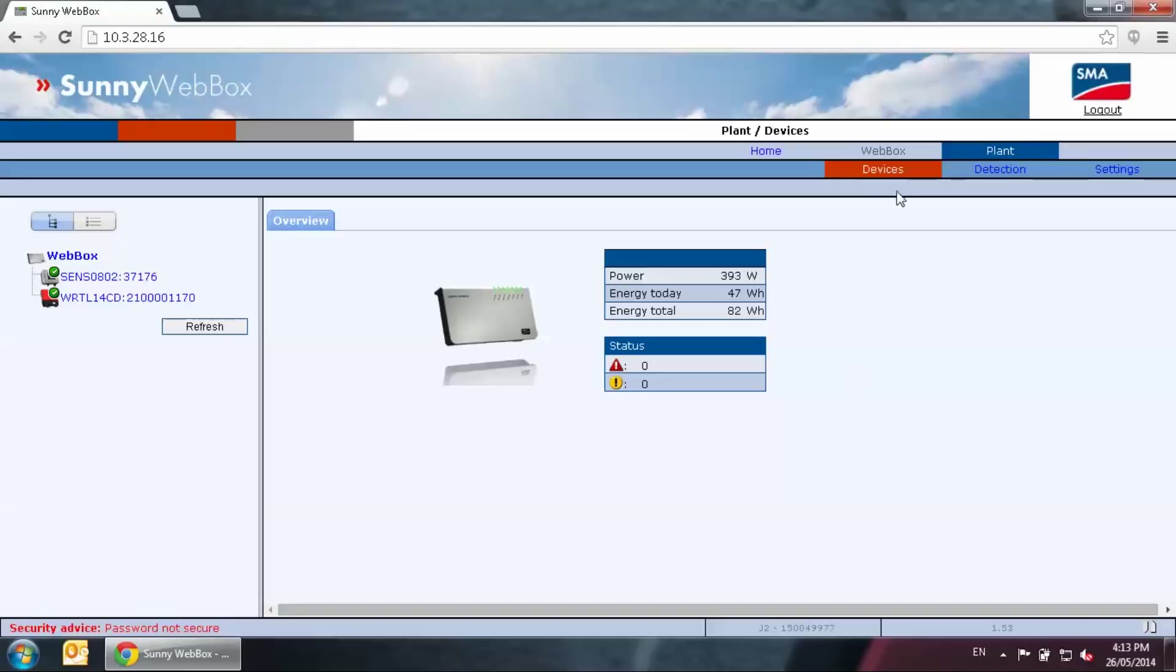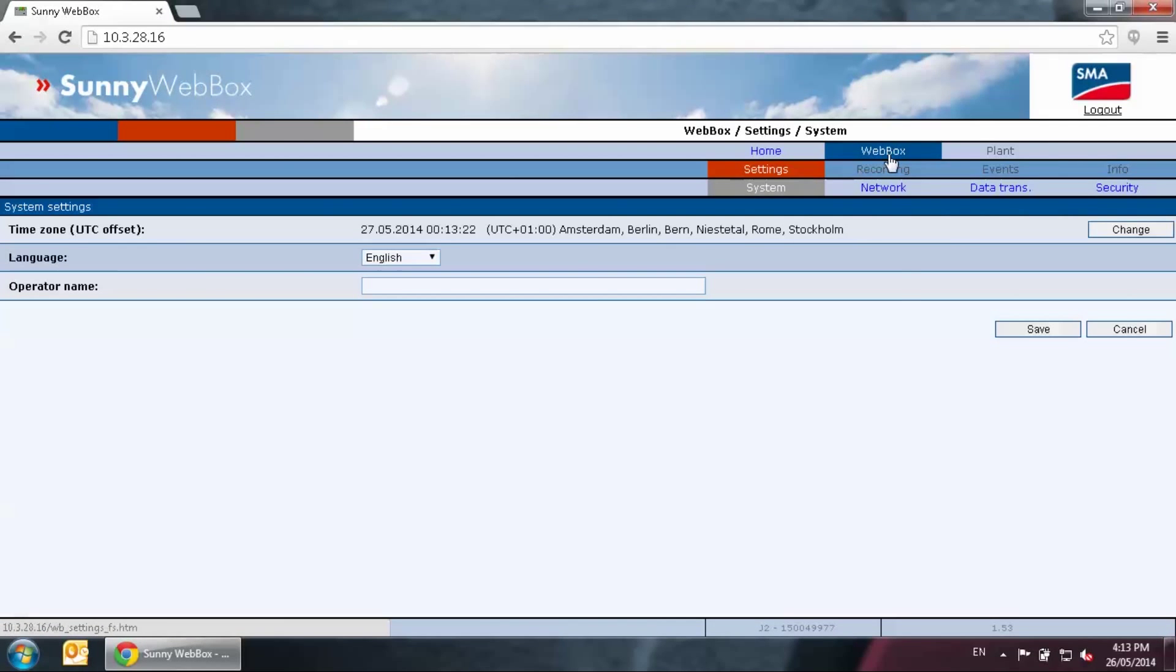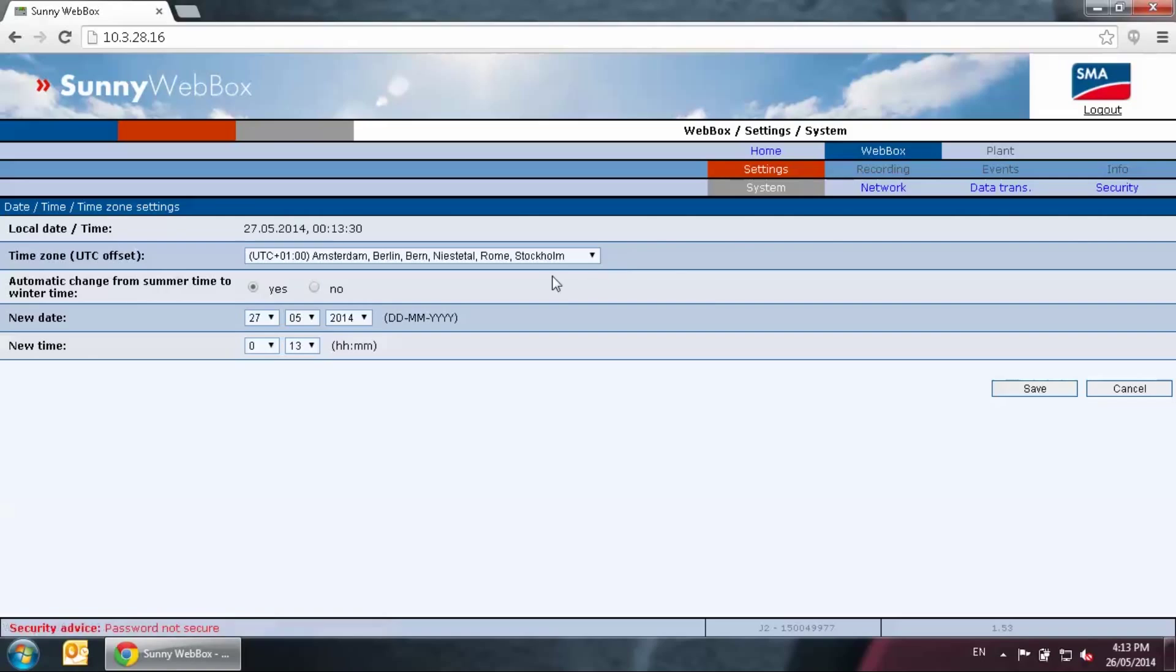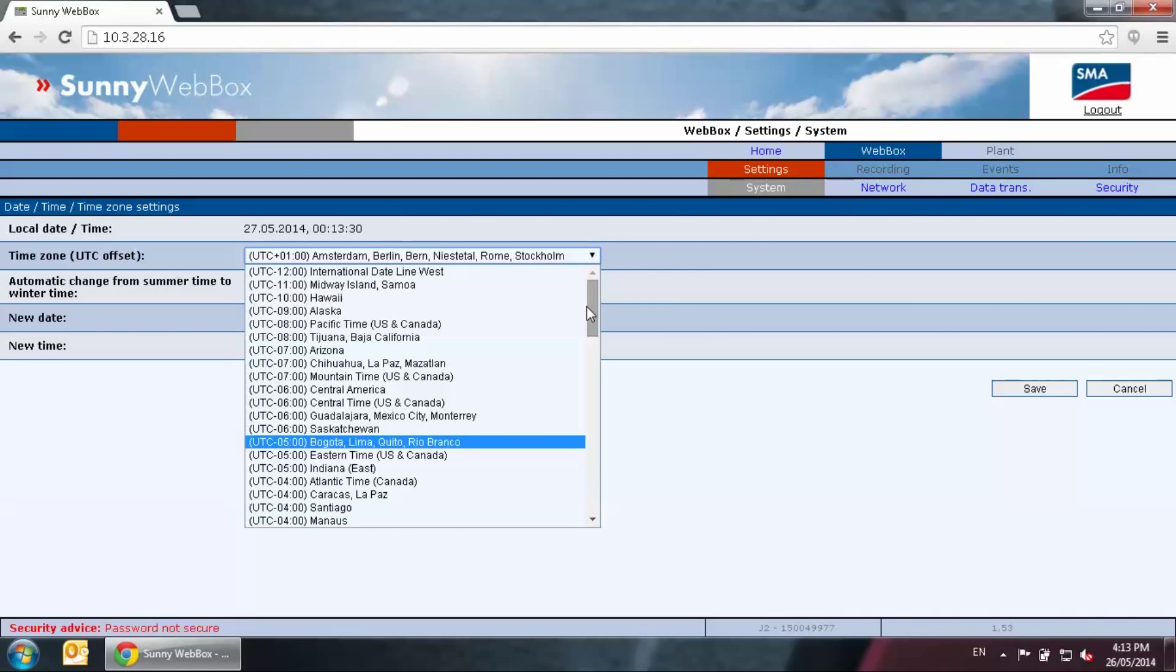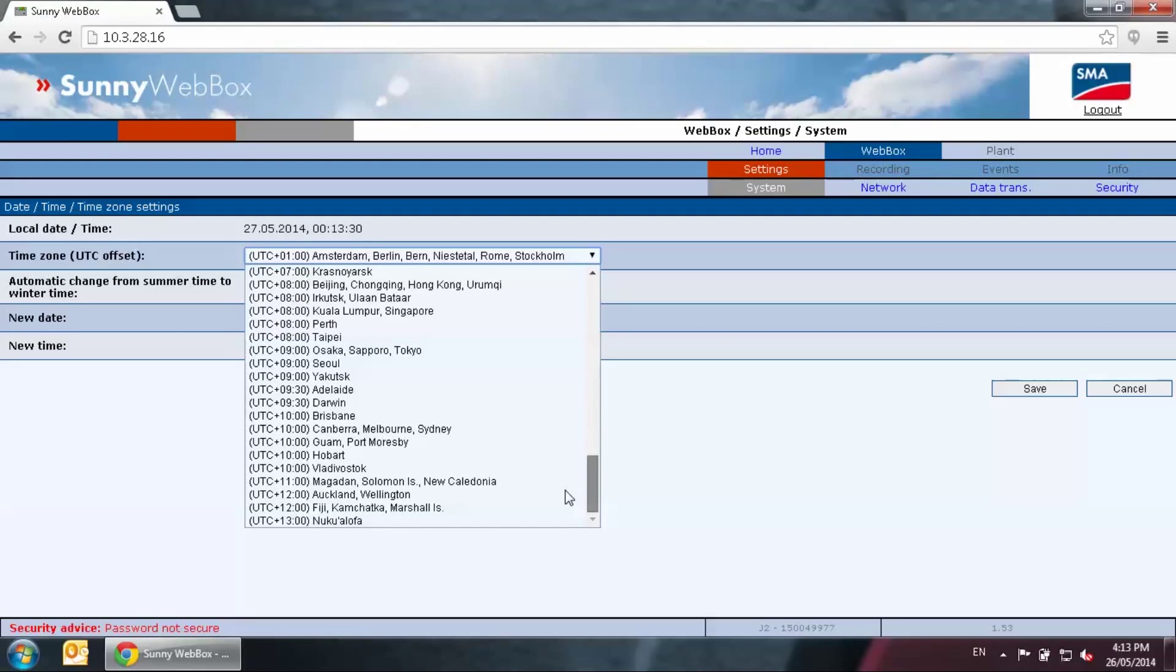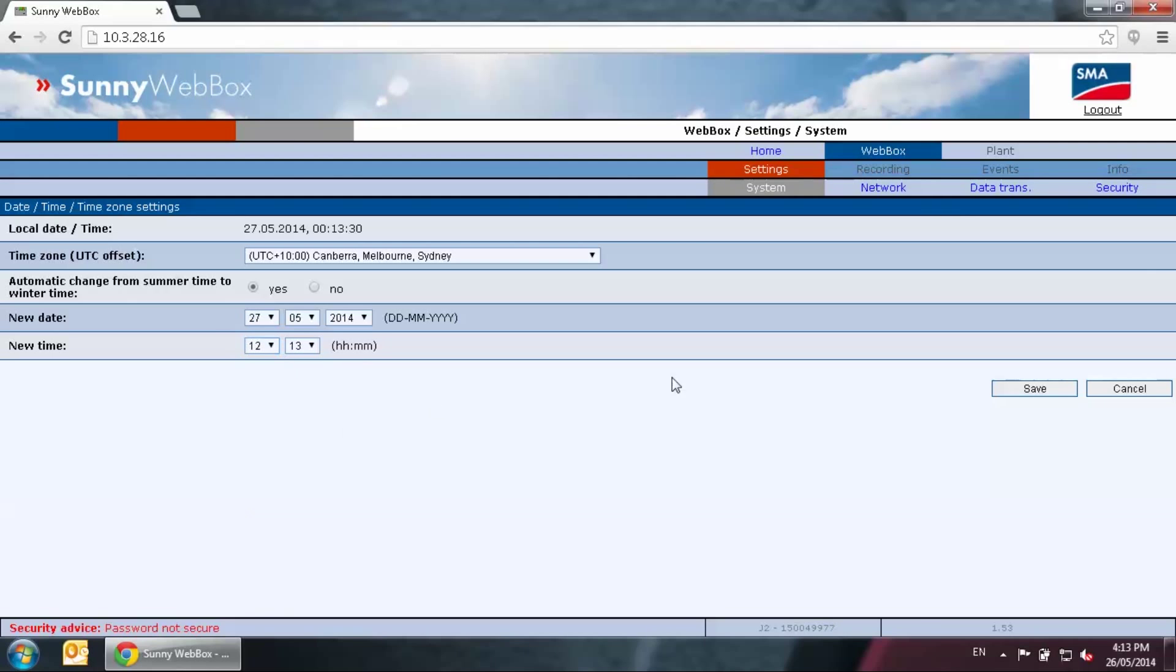First select the web box tab on the top right hand corner, then settings tab. Click on change to change the time zone. This is important. If you have this time zone incorrect, the data in Sunny Portal would be shown generating in midnight. You can also change the time and date and save the screen.